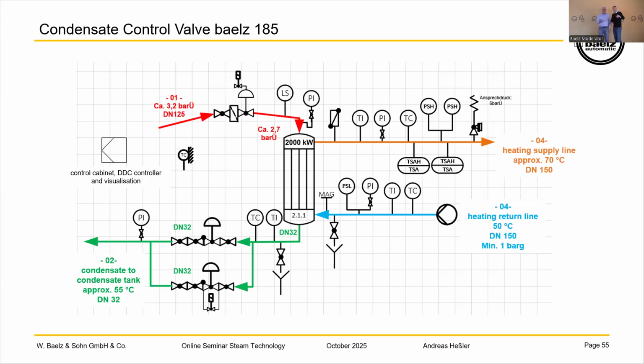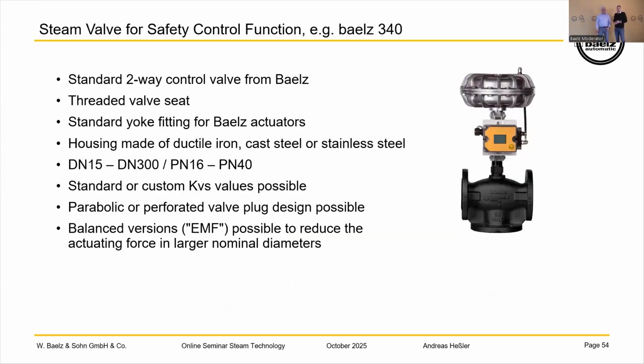Sorry to interrupt you, Andreas. Going back one slide, just to make clear so that there's no confusion about the control valve shown here on the screen. You have a three-way valve shown here. For the two-way version, the BAELZ 340, as it's used as a safety valve or a safety control valve on a steam terminal, there would be a blind flange on the third way. This is the difference between the two-way and the three-way valve. They have the same housing, which makes more standardization. You just use a blind flange to close the third way, but you can also use it as a mixing valve, with or without the blind flange.